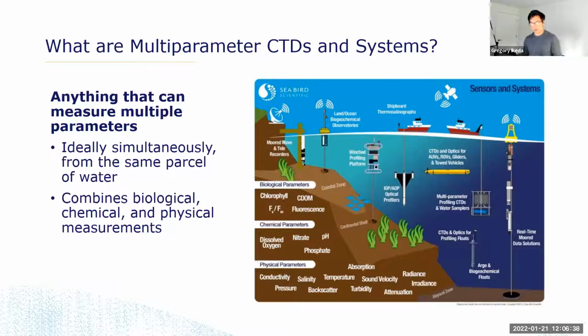While a lot of these are designed to measure just a single parameter, like our optical sensors that might measure just chlorophyll fluorescence, or a dissolved oxygen sensor that measures only dissolved oxygen, a lot of these can be considered multi-parameter instruments because they support several different sensors. You might have temperature, conductivity, pressure, dissolved oxygen, and chlorophyll built into a single instrument and fully integrated, or you have the option to integrate and customize your sensor package to have some pretty diverse sensor types.